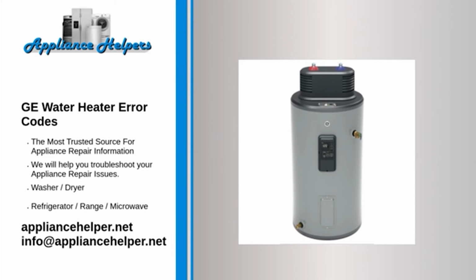Code F9. Problem: lower heating element failure. Fix: disconnect power or unplug the water heater and then check the lower heating element and wiring. Check the wiring and connections on the power control board PCB and lower heating element. Code F10. Problem: upper heating element failure. Fix: disconnect power or unplug the water heater and then check the upper heating element and wiring. Check the wiring and connections on the power control board PCB. Disconnect and measure the heating element for ohm resistance using a multimeter.